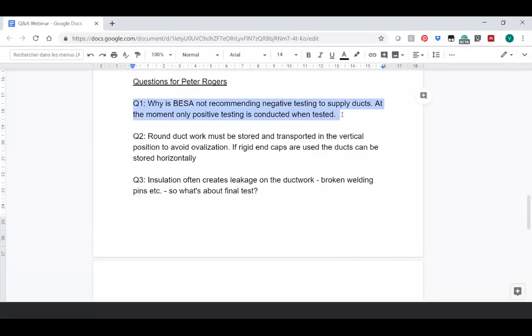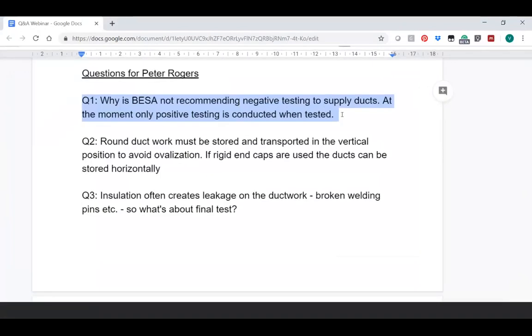The main reason for testing negative ductwork under positive pressure is because if you were to have a negative pressure on a system of 200 pascals, you could possibly cause collapse of the ductwork system. It's not constructed to take suction under that high pressure. There have been instances where, when the ductwork is blanked off, it can very easily collapse under that negative pressure. That's why it's always done under positive pressure testing.